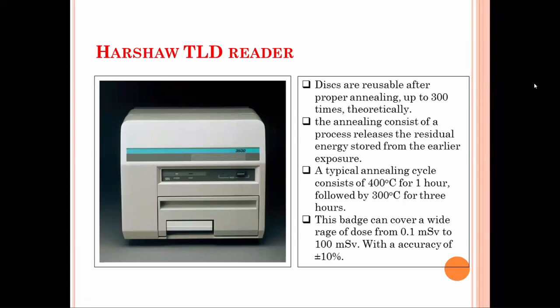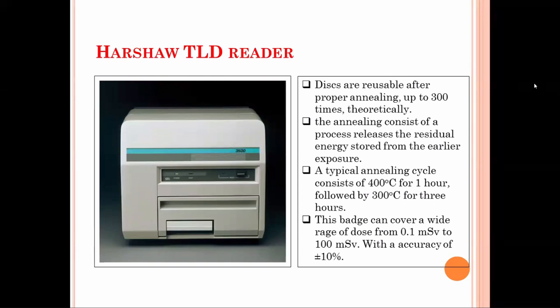When changing TLD cards each quarter, an annealing process must be performed. If the TLD contains some residual dose, it is removed through annealing: first heating the dosimeter at 400 degrees Celsius for one hour, then at 300 degrees Celsius for the next three hours. This removes all residual dose from the dosimeter. Theoretically, a thermoluminescence dosimeter can be used up to 300 times, though in practice it is changed when changing institutes.